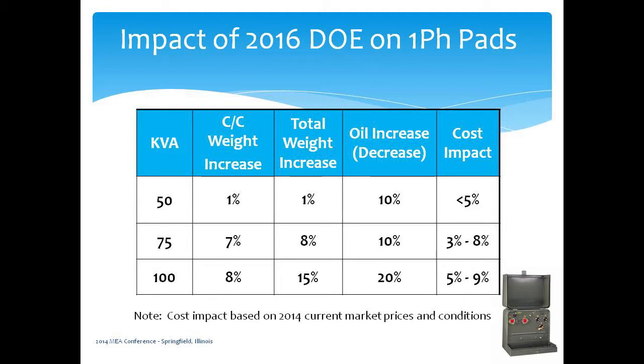Other manufacturers, you may see other differences because they're going to have to go to a larger tank, more oil, more weight impact. So this gives a bit of a difference of what we're going to see on the single phase pads. You're going to see somewhat of an increase, but it depends on how the unit is built, whether it's a top load or a back load design. Top loads, you're probably going to see more of an impact. Back loads, you'll probably see less of an impact.